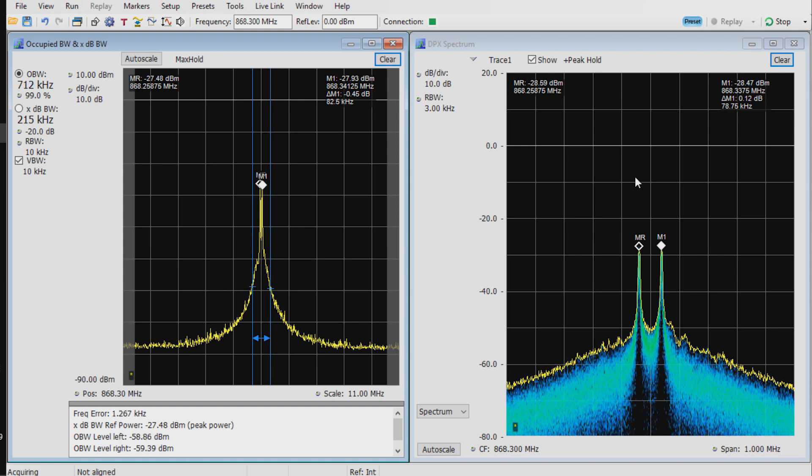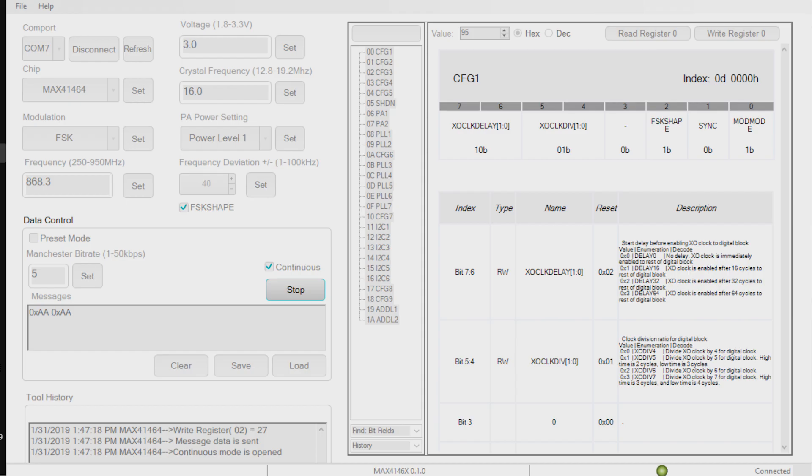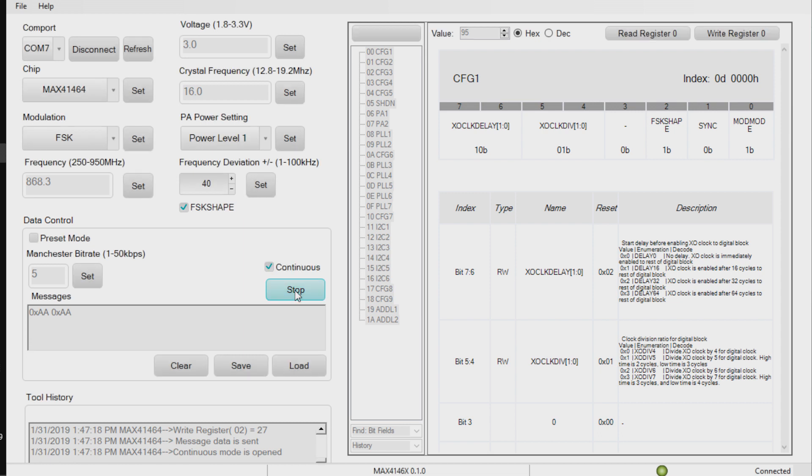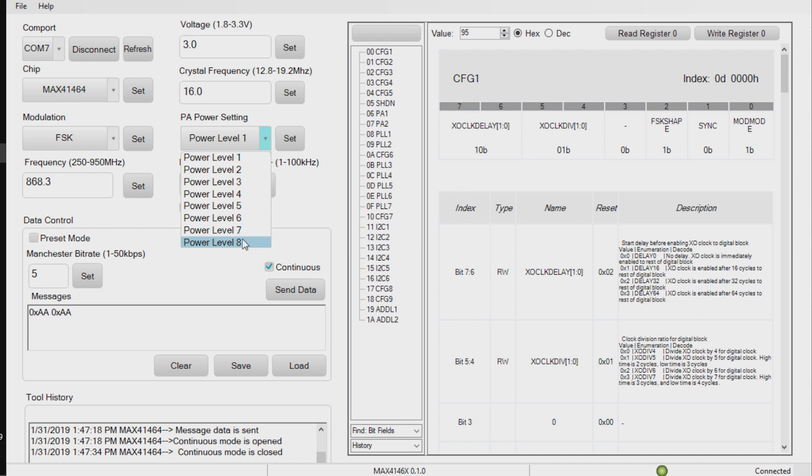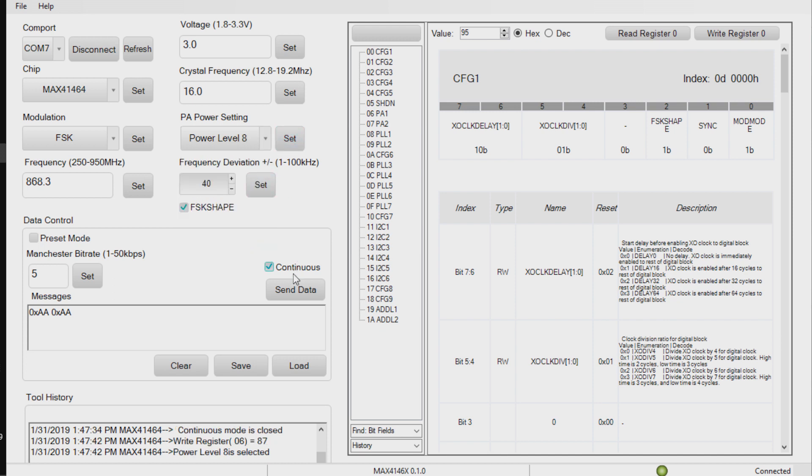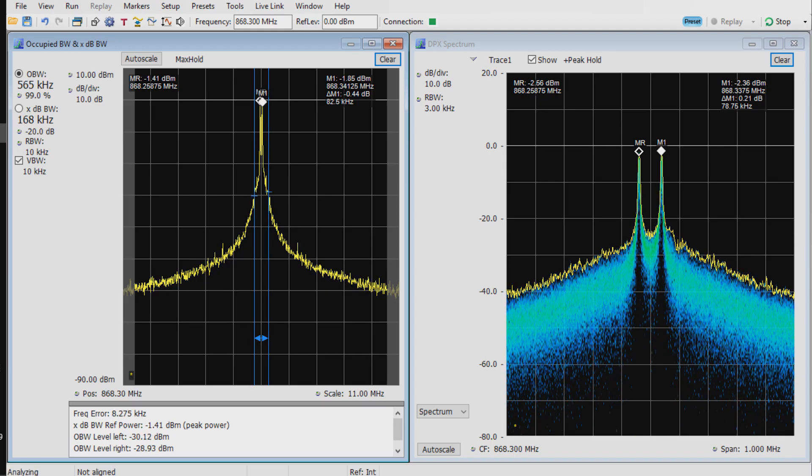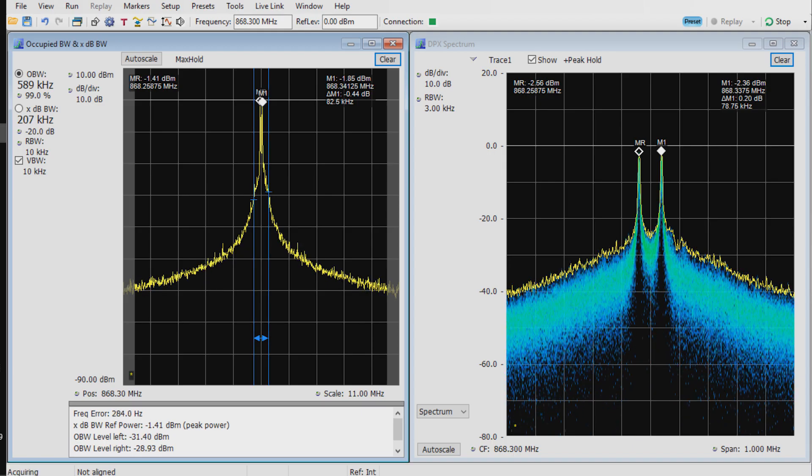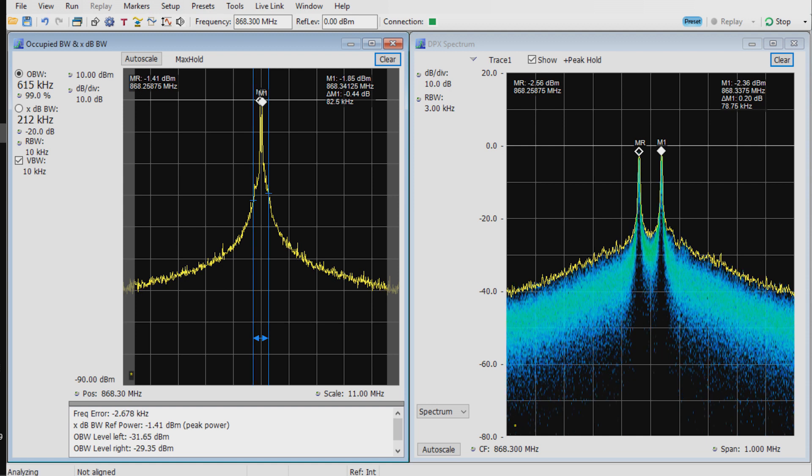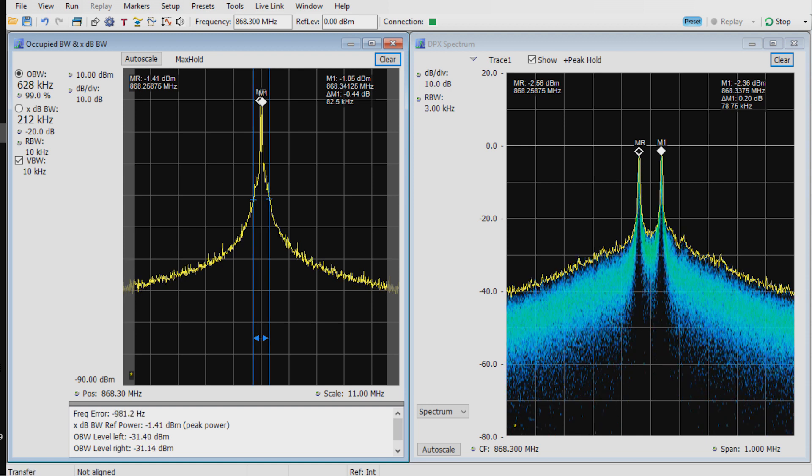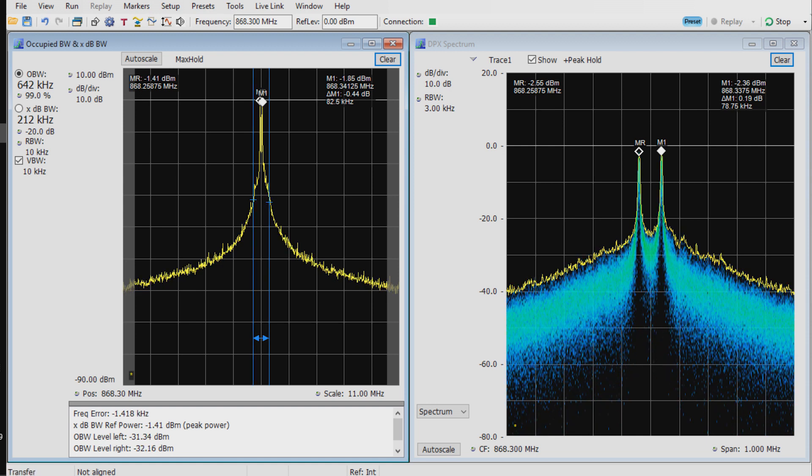As a quick demonstration of some of the software and the device capabilities, I'll just stop the data stream. I'll go and select the higher power setting for the device, set that, and we'll start the data stream again. We'll go to the spectrum analyzer, and you can see that the peaks on the frequency FSK deviation are now much higher.